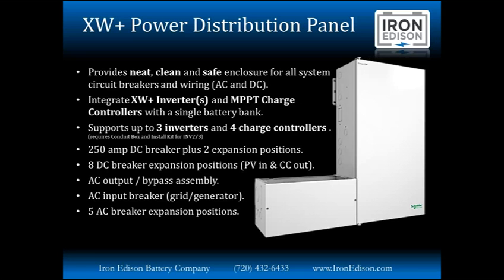It comes with a 250 amp DC breaker for the first inverter, plus there's room for 2 additional 250 amp breakers for inverter number 2 and inverter number 3. There's 8 DC breaker expansion positions for the charge controllers. You can have 4 PV input circuit breakers and 4 charge controller output circuit breakers. We've also done applications with up to 8 charge controllers using the XW Power Distribution Panel.